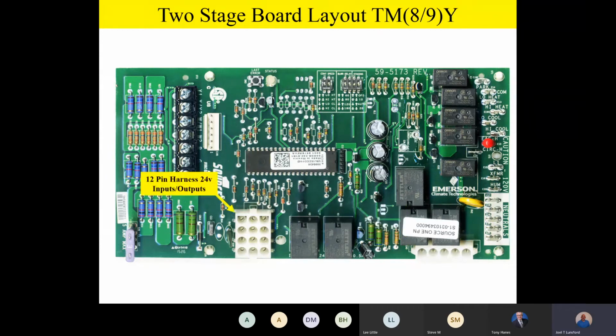There's our 12-pin harness with our 24 volt inputs and outputs to our gas valve, our pressure switches, and our safety circuits. In the lower left-hand corner of the board, you'll notice there's a 3-amp fuse for 24 volt on-board protection. You'll also please note that we ship it with a 3-amp fuse. But if you look at the silk screen on the board itself, 5 amp is the maximum permitted fuse on that. So we do give you an onboard protection of 3 amp, but you can go up to 5 amp if necessary with that fuse.